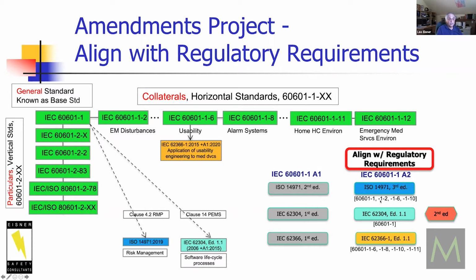The notation down here in brackets will tell you what standards in the series of 601 standards up here reference normatively, meaning required, not informative, being not required, but guidance, 14971. So risk management is throughout a lot of the series of these standards that we dealt with in the amendments project: the general standard, the EMC standard, the usability standard, and the physiologic closed loop standard. I'm surprised it's not in this one actually, but I guess it isn't.